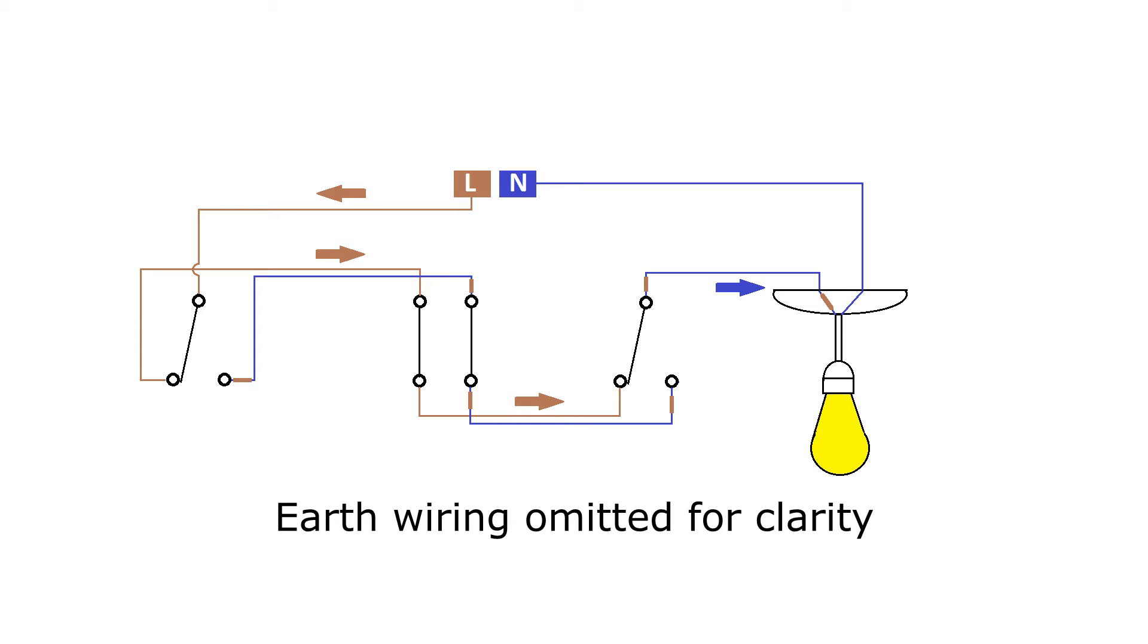For this method, the line conductor goes to the switch at one end of the run and is connected to the common terminal on the switch. The switched line conductor is taken from the switch at the other end of the run. The incoming line conductor could come from the same ceiling rose and just take a different route. Or it could just as easily come from a junction box or a neighbouring switch in a multi-gang switch.